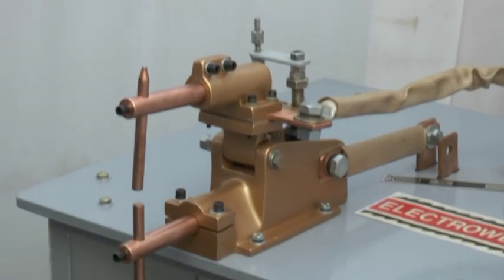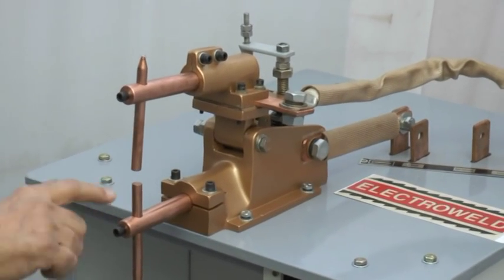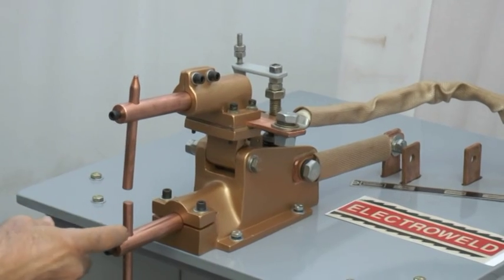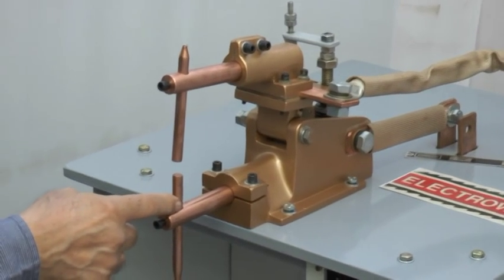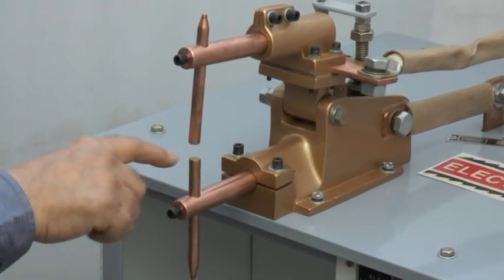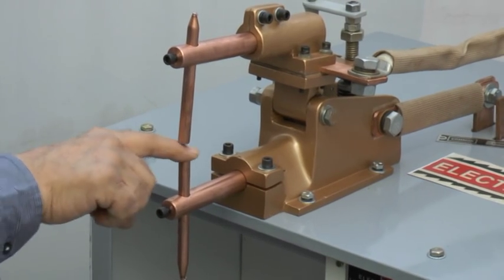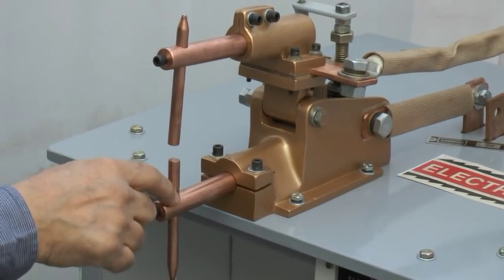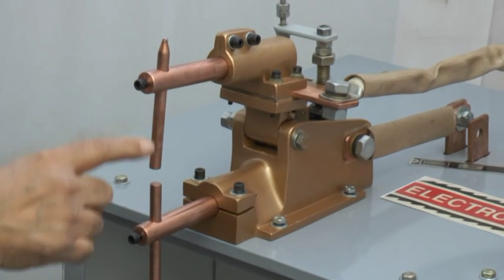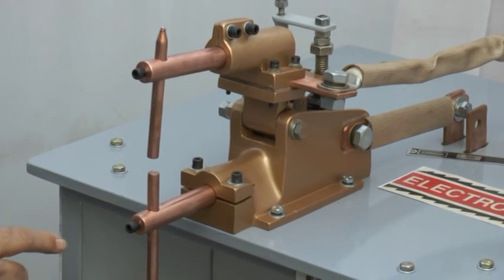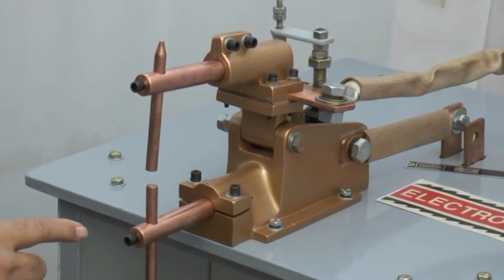After using this machine for some time, carbon accumulates on the electrodes and in the holders. So you remove these electrodes and apply emery paper here and here so that they are cleaned of any rust or oxidation.